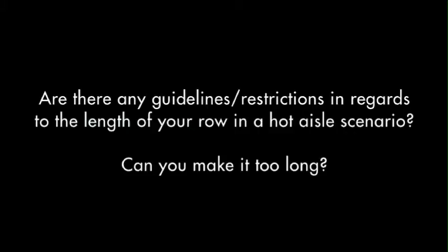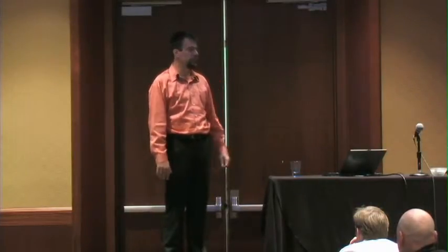You can make it too long. From any one point, you have safety standards, human safety standards around an egress. If you're considered a room within a room, now you have to have an egress within so many feet. And what is that? That's going to change. On average, we don't see an IT rack row longer than 20 racks or 40 feet. On average, if you had a 100,000 square foot data center, I would not expect to see rows 30, 40, 50 racks long. It would be unrealistic. And again, if you're going to heat containment, you want an aisle for serviceability, and your perpendicular wire trays.